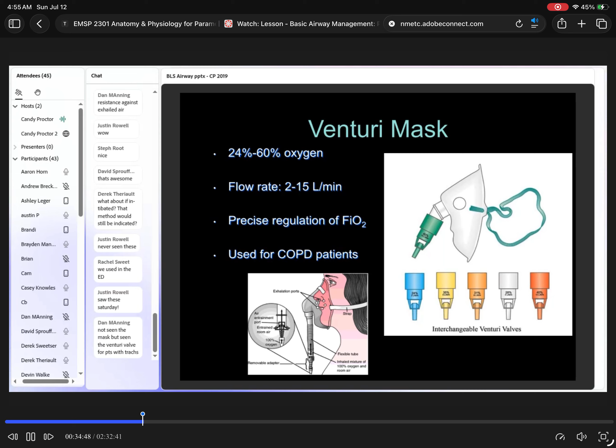So you saw these on Saturday. They're color-coded, telling you how many liters to put through and the precise percentage you'll get out. They work by the Venturi effect: as gas moves through the device into the mask, it creates a vacuum, sucking air in through the side vents at a very standard amount. So it's the mixing, by way of the Venturi effect, of room air being pulled in through those side vents, based on which valve you have and the liter flow, that gives you a precise amount.